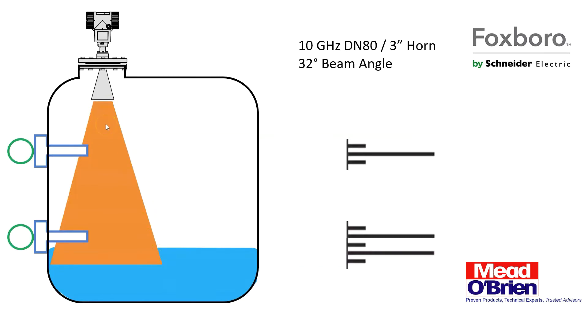Now every radar I'm aware of on the market can actually blank out obstacles. So if you see my crudely drawn thermal wells here protruding into the tank, this radar might project its beam and it might say, hey, at this height I see an obstacle, this thermal well. And at this height I see an obstacle, a thermal well. And then I also see the actual liquid level we're trying to measure.